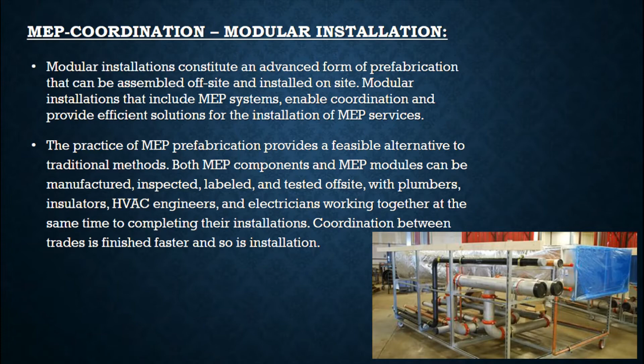So modular installation is getting importance in construction as the trend moves on, because building information modeling enables the modular installation process in a more efficient manner. The practice of MEP prefabrication provides a feasible alternative to traditional methods. Both MEP components and MEP modules can be manufactured, inspected, labeled, and tested offsite with the plumbers, insulators, HVAC engineers, and electricians. Coordination between trades is finished faster, and so is the installation. So it is highly recommended to proceed with modular installation in all the sites where it is possible.